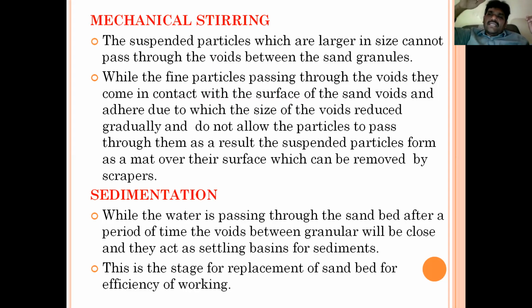Whereas in the first case, the largest substances are stuck on the voids on the above surface, on top of the sand itself. So the action will be reduced or may stop. But here in these voids, sometimes while water is passing through, after a period of time, the small organic materials in that wastewater, or in the water being filtered, will adhere to the voids of the sand granules.